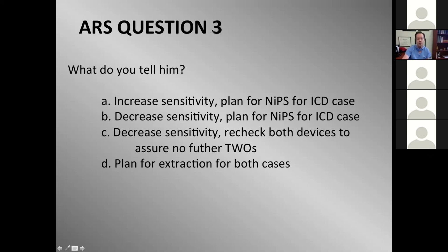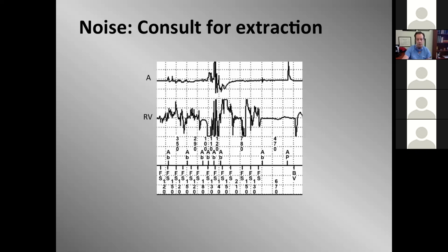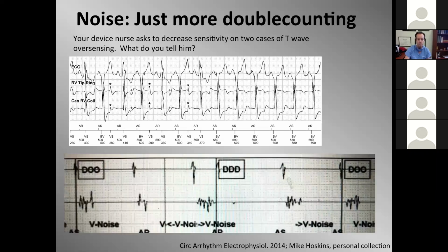But it's very important to remember that if you have a conductor fracture or some through and through electrical contact that should not be there due to insulation breach, in a beating heart, frequently that will result in a cyclical noise pattern. So that ventricular systole generates that contact, recontact noise. And so just because it's cyclical does not mean it's not a conductor fracture.